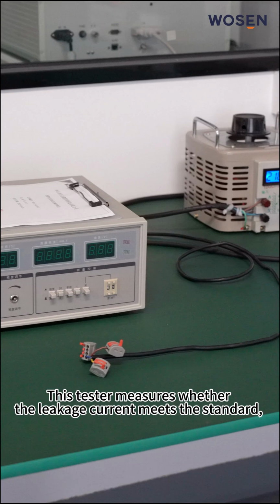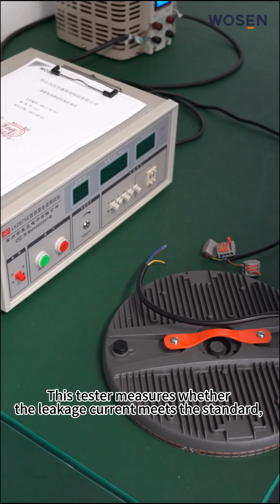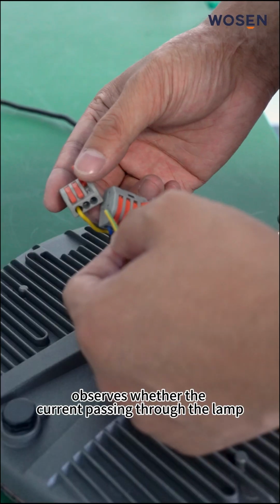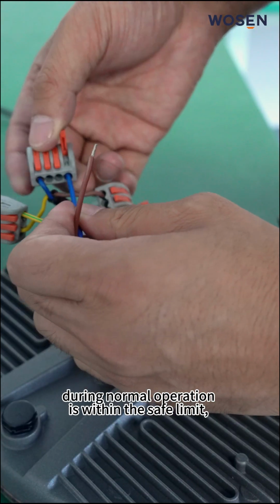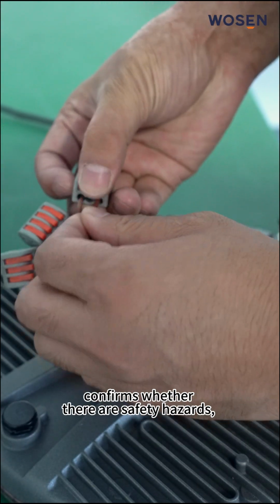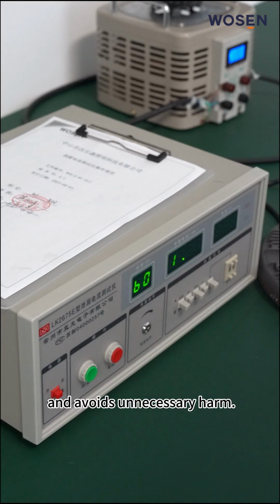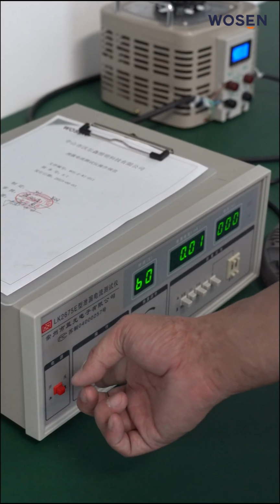This tester measures whether the leakage current meets the standard, observes whether the current passing through the lamp during normal operation is within the safe limit, confirms whether there are safety hazards, and avoids unnecessary harm.